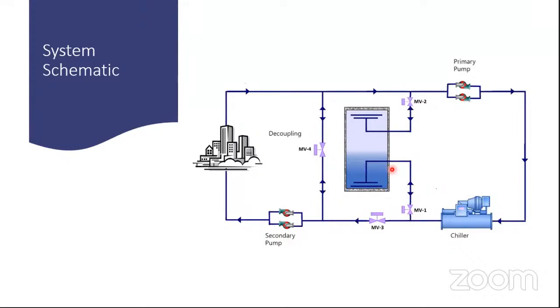Like in the density difference, we understand, like in stratification, the cooler water will stay at the bottom and the warmer will stay at the top. So that is how natural stratification would happen. So the discharge always takes place from the bottom. So from here the chill water will be drawn, for a case when chiller and thermal storage both are cooling.